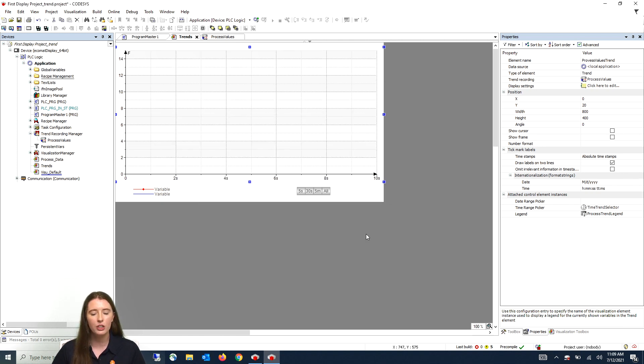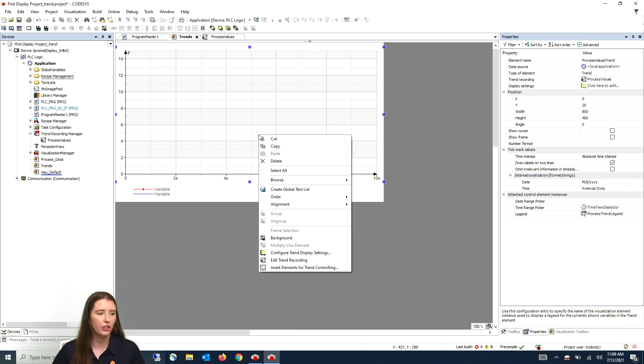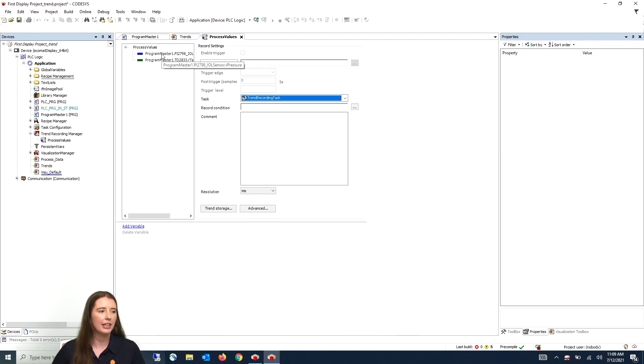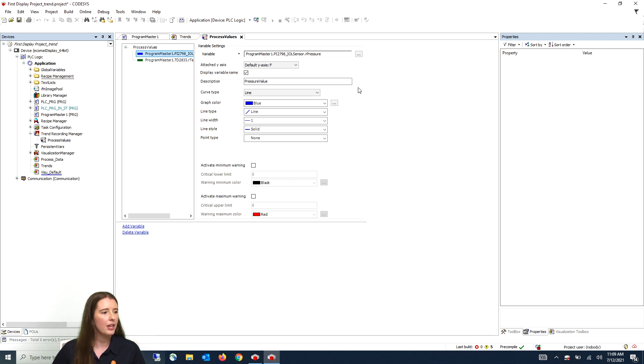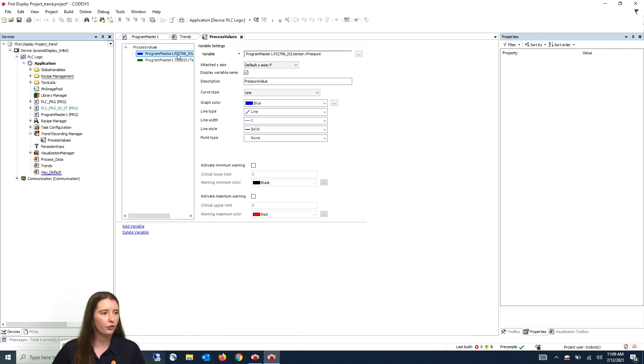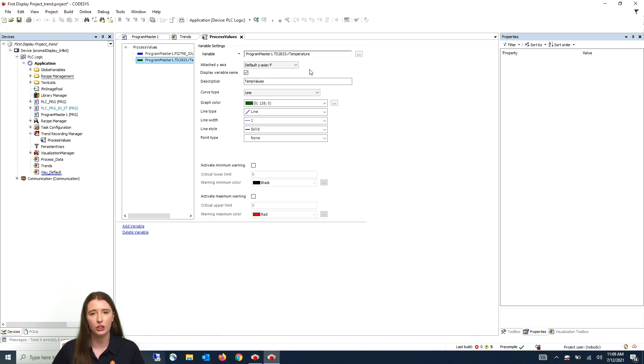You are then going to right click on the trend again and select edit trend recording. Here you will select each of your process data values and where it says attached Y-axis assign the correct Y-axis. For our pressure element we will select PSI and for our temperature element we will select degrees Fahrenheit.